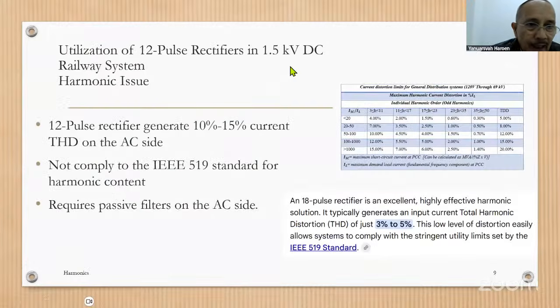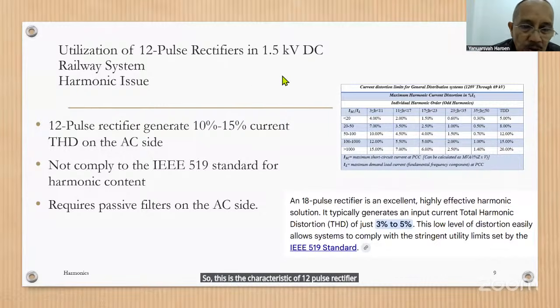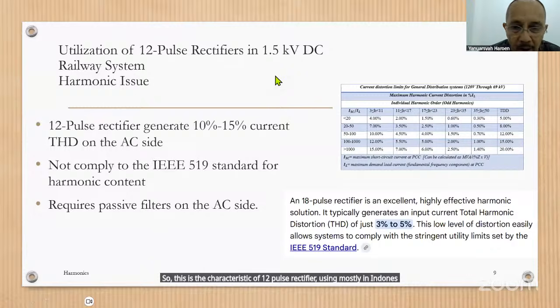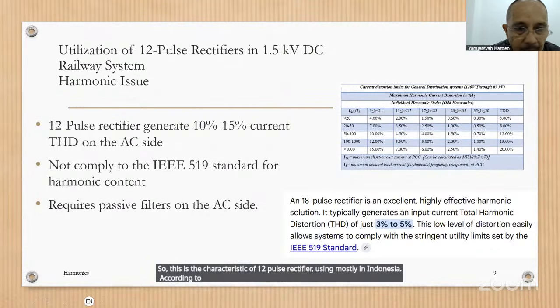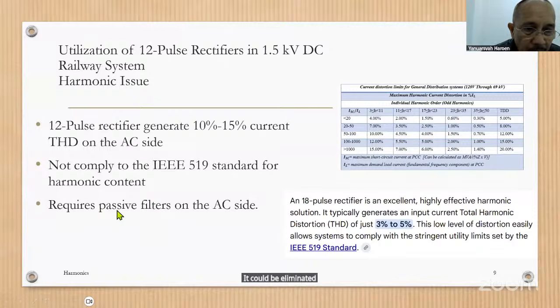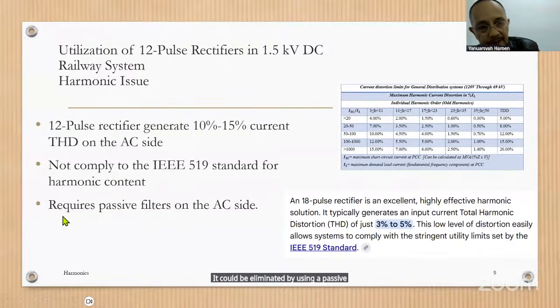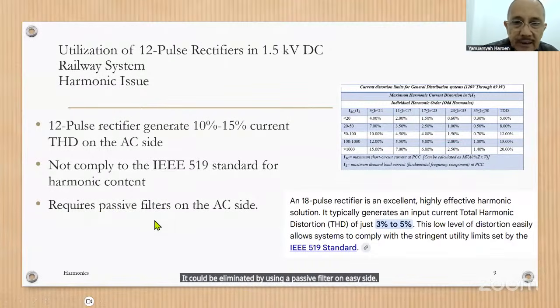This is the characteristic of the 12-pulse rectifier mostly used in Indonesia. According to IEEE 519, the harmonics are still not fully compliant, but this can be eliminated by using a passive filter on the AC side.